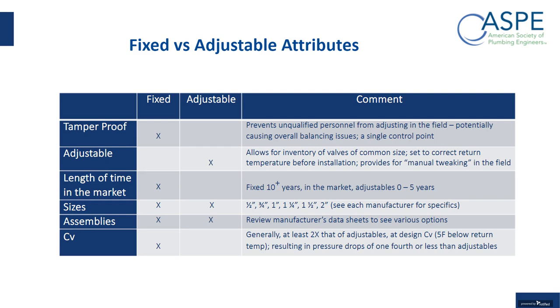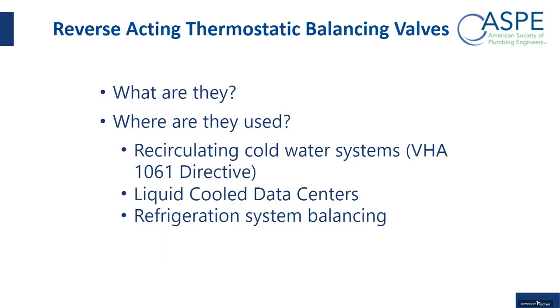And then assemblies, there are a number of manufacturers that have assemblies with shutoff valves or strainers or check valves or things like that built into them. And then the fixed has definitely a higher CV than the adjustable. Again, something just to keep in mind.